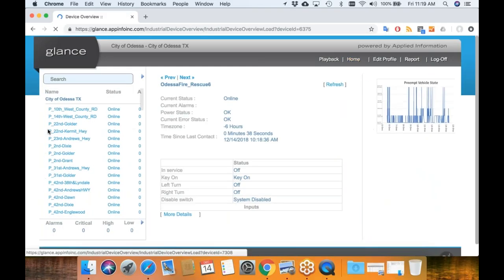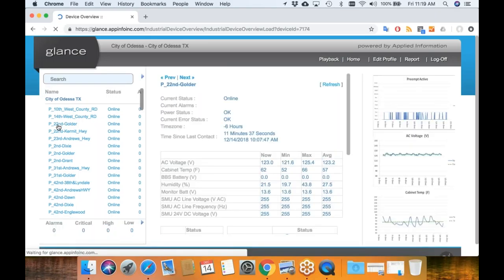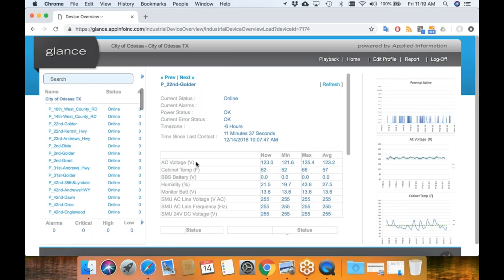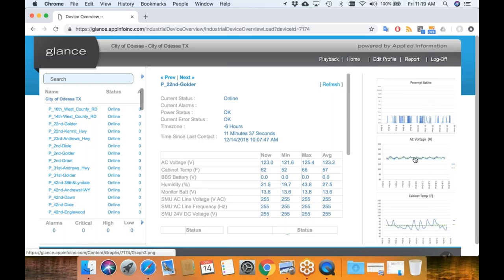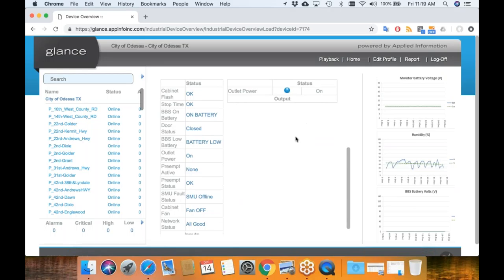The other thing to go to is an intersection. You can click on an intersection on the map or on the left-hand side, and it will bring up information for that traffic signal — the AC voltage, cabinet temperature, BBS if they have one connected, humidity, internal battery, and the conflict monitor information if they've got it hooked up. On the right-hand side you're looking at when the preempts were active, AC voltage, cabinet temperature, humidity in the cabinet, BBS. From this cabinet I can see that they don't have a BBS set up, so we should probably change the device type. The cabinet fan is off at the moment, preempt status is OK, network status is all good.